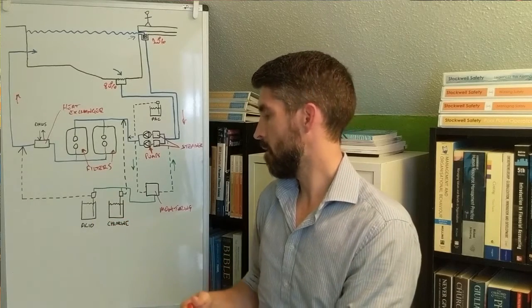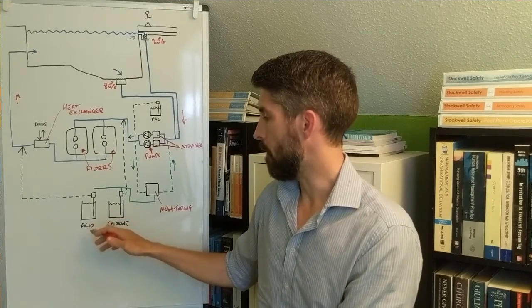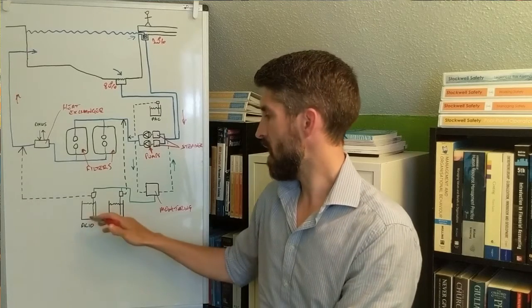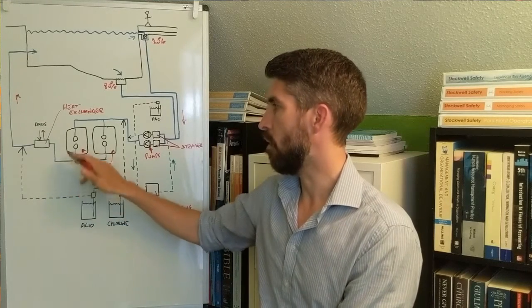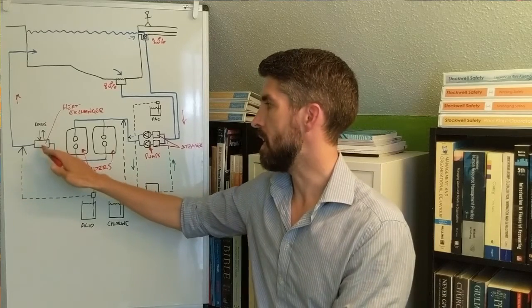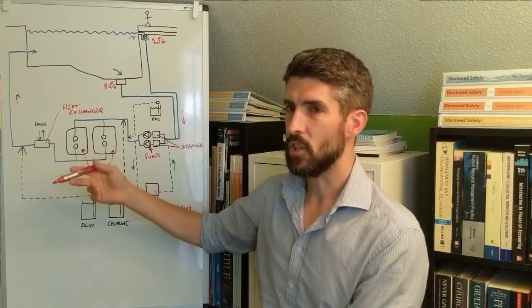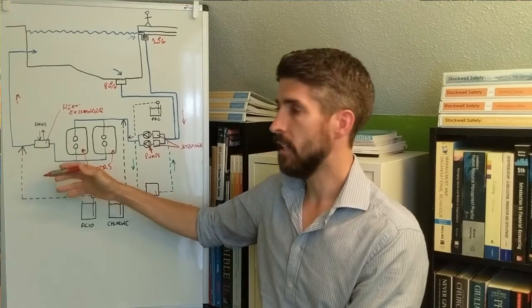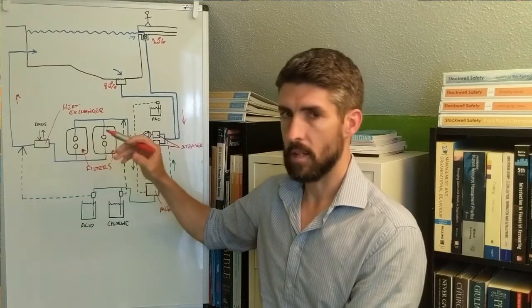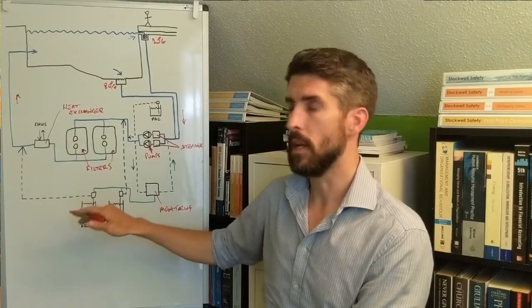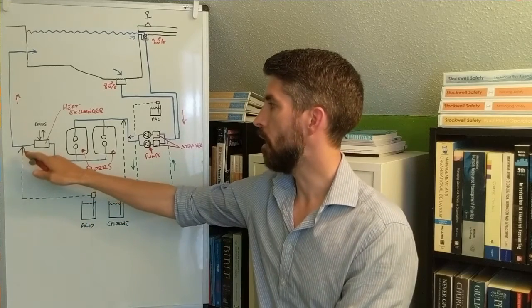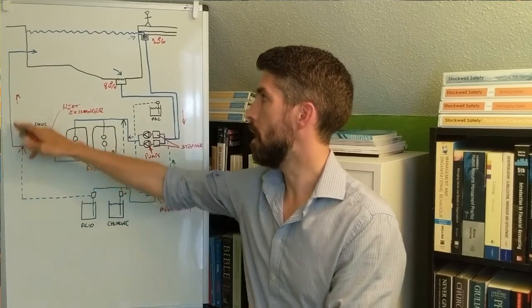Then the acid is being dosed in after the filters, which is fairly typical, because acid, having the properties acid does, it wouldn't be advantageous to be dosing the acid prior to, for example, the heat exchanger, because the heat exchanger would come under a corrosion attack.